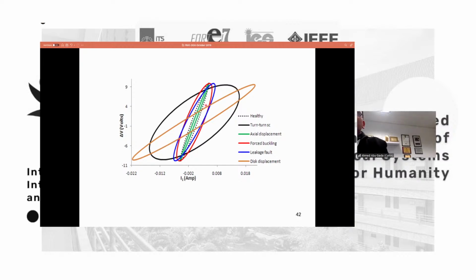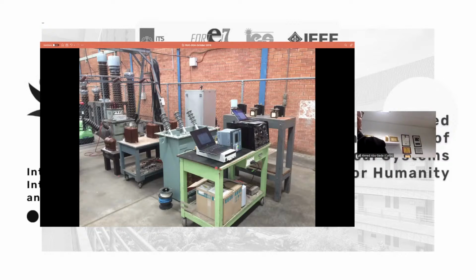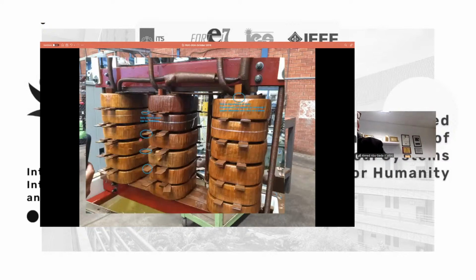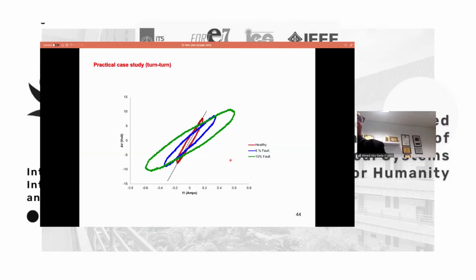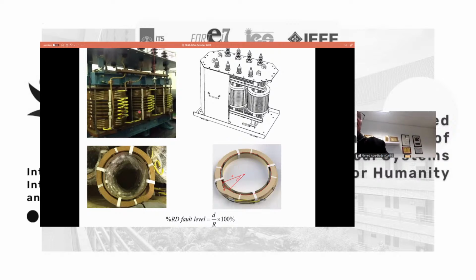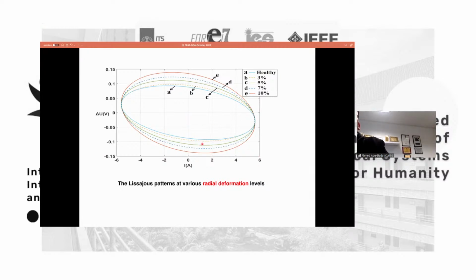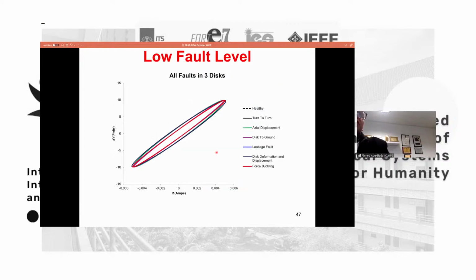We have also done some practical measurements on a custom-made transformer where you can access the winding outside. You can create space deformation between the windings by removing spacers, or move them up, down, or in the radial direction. We found the practical results are almost identical to what we achieved in the finite element analysis. We also did this on a bigger transformer and created many faults, and the results were similar to the simulation stage.